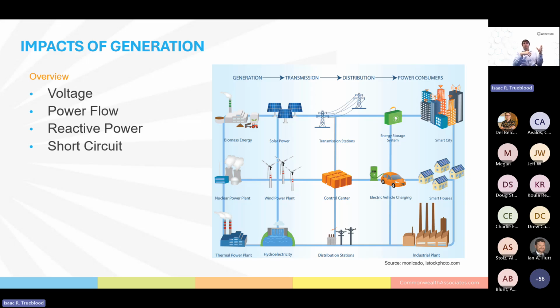Additionally, the high voltage nature of the transmission system allows for the whole system to be strong and electrically close. This allows for unexpected variations in the load and generation to be more evenly spread across multiple generators. There are always exceptions, but overall, the transmission system is resistant to many of the impacts of generation. I will stress it does not mean generation connected to the transmission system does not have these concerns, just that they are lessened due to the nature of the transmission system when compared to distributed energy resources. Some of the impacts of generation I will go over in this presentation will be voltage, power flow, reactive power, and short circuit.